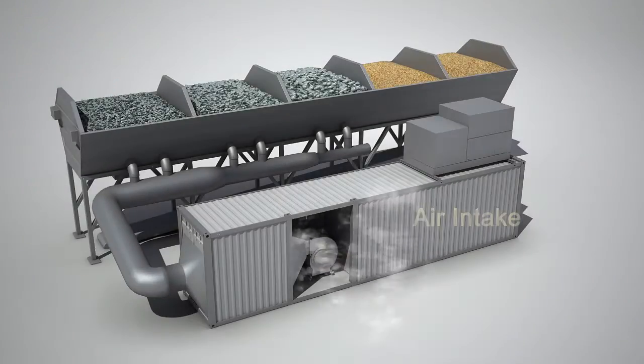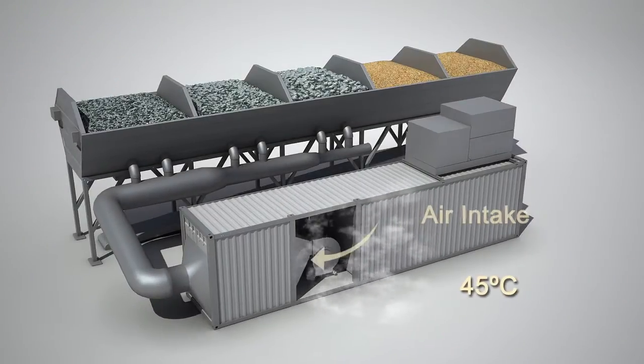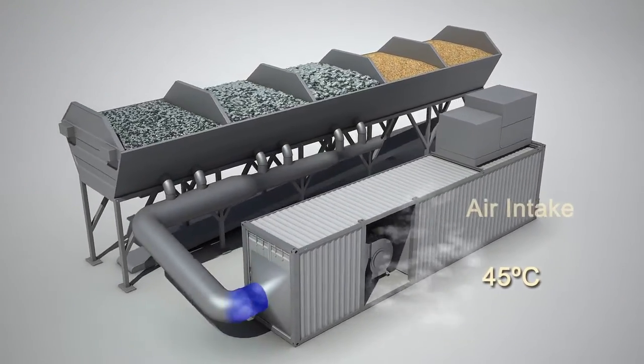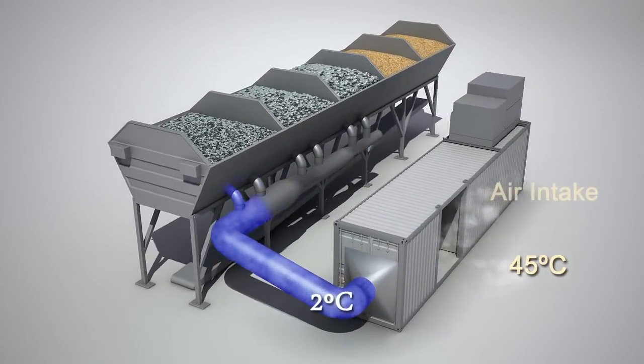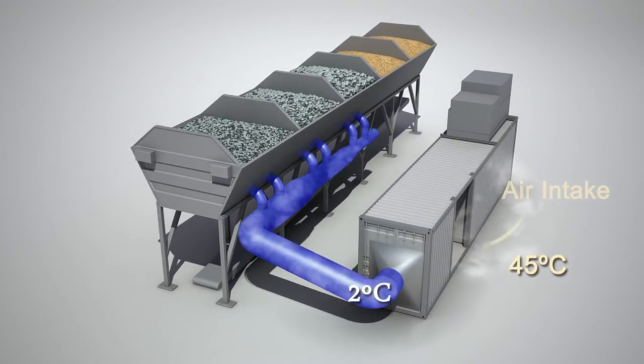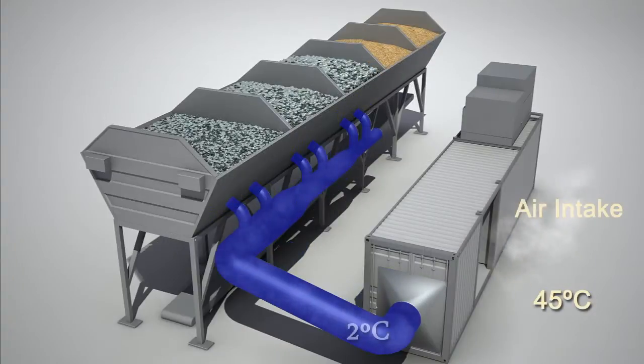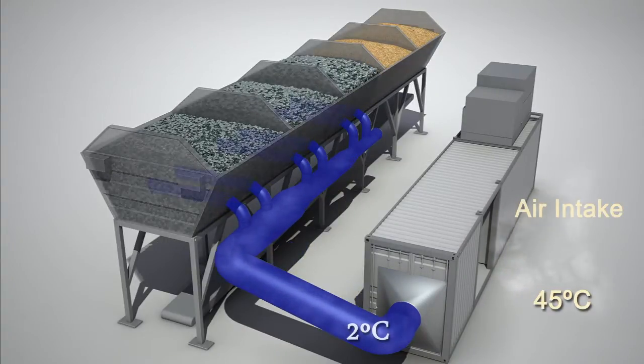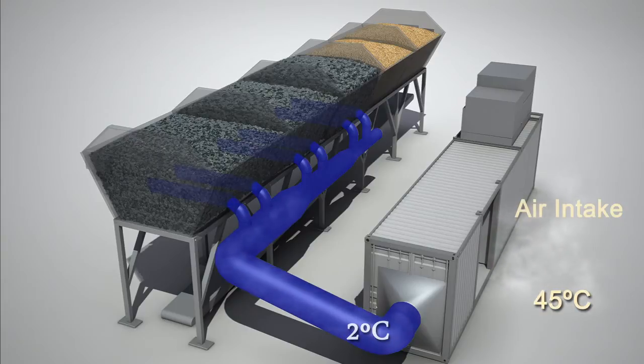Aggregate cooling by air is an efficient concrete cooling process when there is a limitation in water content specified in the concrete mix or specified by the contractor or consultant. The components of the system include a multi-stage air cooling unit, high efficiency blower with air nozzles, ducting and air filters where necessary. Pressurized cold air is circulated through the inline bins or vertical silos holding the aggregates.